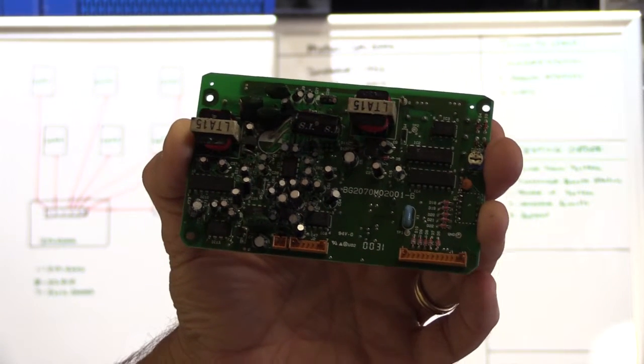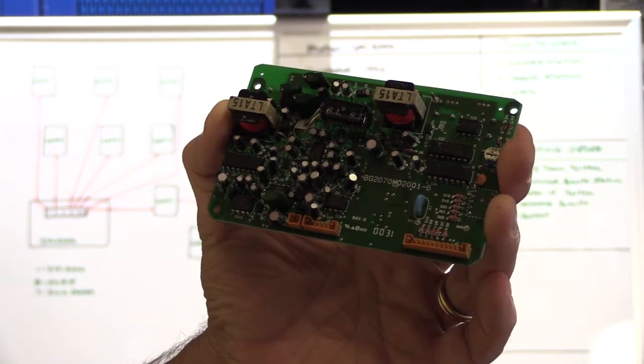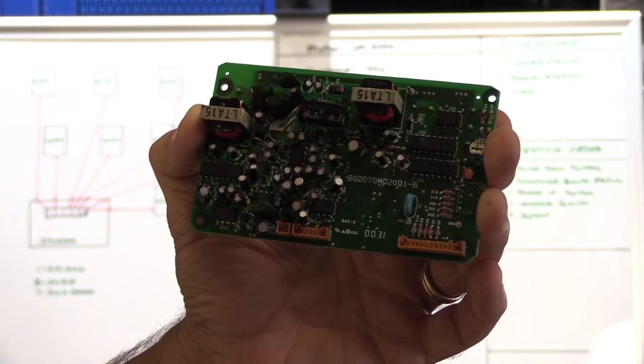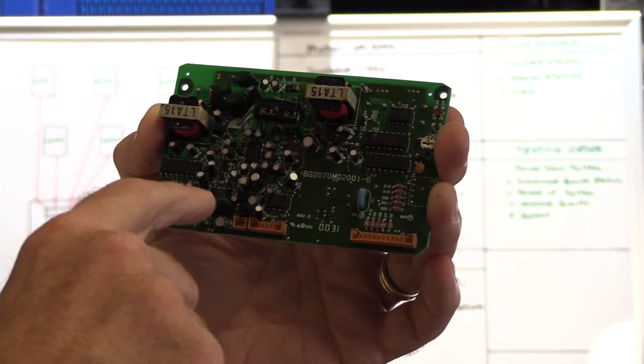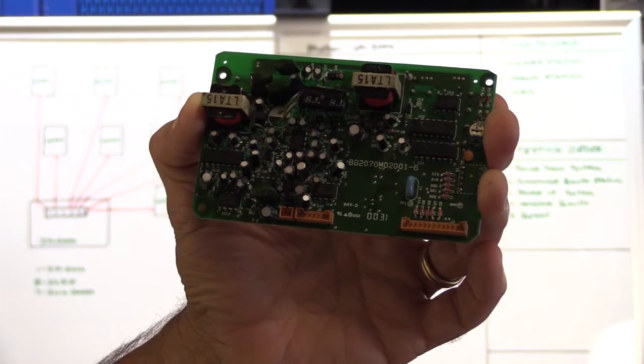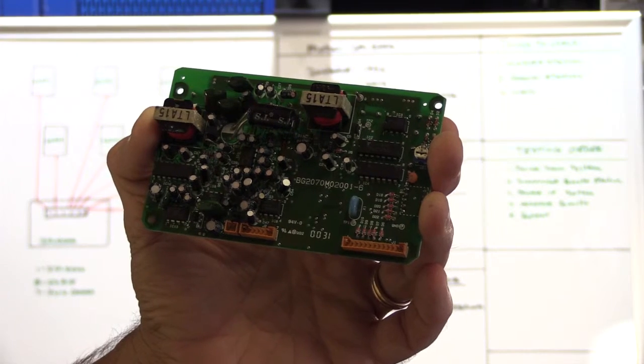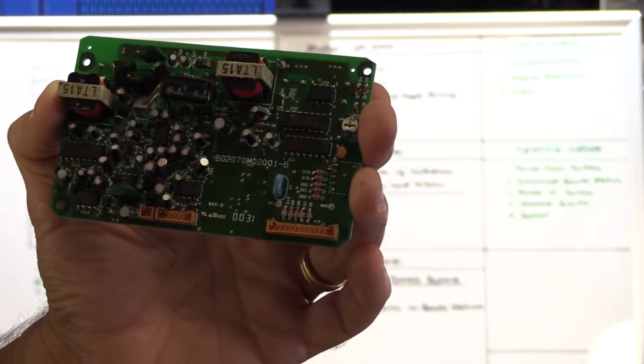So there's a lot going on in these types of stations, and these boards can have intermittent failures or flaws in them, and that can cause the exact kind of problem that this customer was experiencing. An individual remote station with some bad components can be creating the static noise that's on his system. So troubleshooting a system like this is not a trivial thing to do. You have to be very methodical about how you go about it. So let me explain to you how you do that.